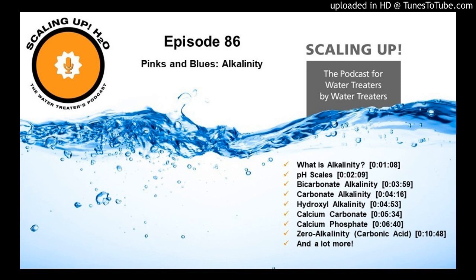Now, a lot of you might have a test. There's a barium test that you test directly for hydroxyl alkalinity, but a lot of us do 2P minus M. Now, remember at the top of the show, I said we have multiple terms for everything in water treatment. Well, let me share some other ones with you. Now, I use the terms carbonate and bicarbonate alkalinity. Bi in this case means hydrogen. So we have hydrogen in one, we don't in the other.